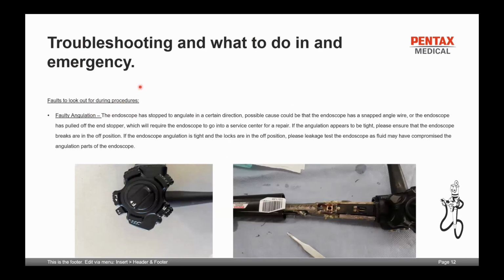Okay, faulty angulation. That is a common occurrence with flexible endoscopes as well. Sometimes you'll get called into a theater and the doctor will complain that the endoscope has stopped angulating in a certain direction, or it has potentially become tight or stiff. If your angulation has stopped moving in a certain direction, the possible causes are that you've either got a snapped angle wire or the endoscope has pulled the end stoppers off, which will then require the endoscope to go in for a repair at a service center.